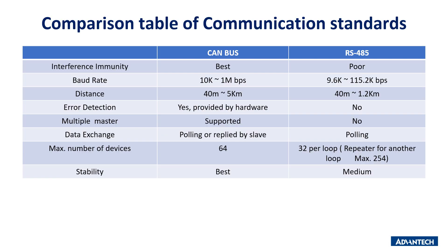Comparing CAN bus and RS-485: CAN bus has better noise immunity, supports higher transmission speed over distances up to 5 kilometers, provides error detection caused by channel noise, and offers multiple master mode. However, CAN bus can only support a maximum of 64 devices, whereas RS-485 can support up to 254 devices with the help of repeaters.